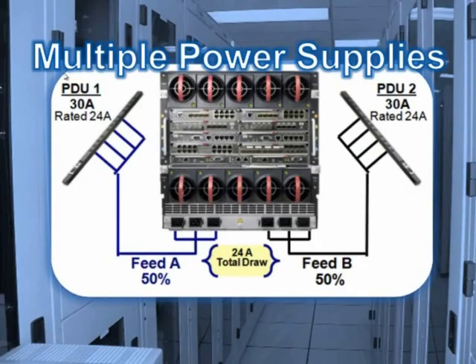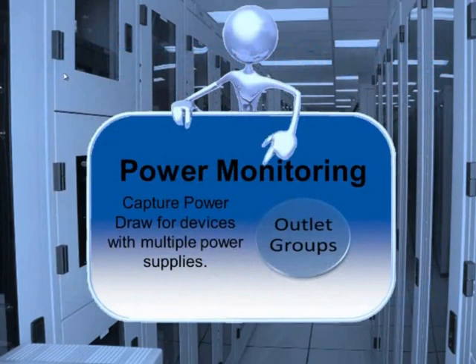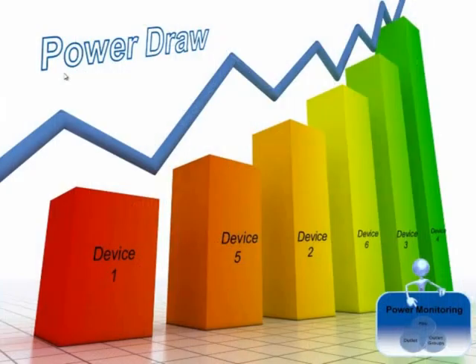Many servers and switches have multiple power supplies, and the ability to aggregate data from all of the power sources is important. PDUs that allow you to create power groups show you the power draw information for devices with multiple power supplies. By being able to chart the exact power usage of all of your devices, you can compare various servers and easily identify older, less efficient servers.